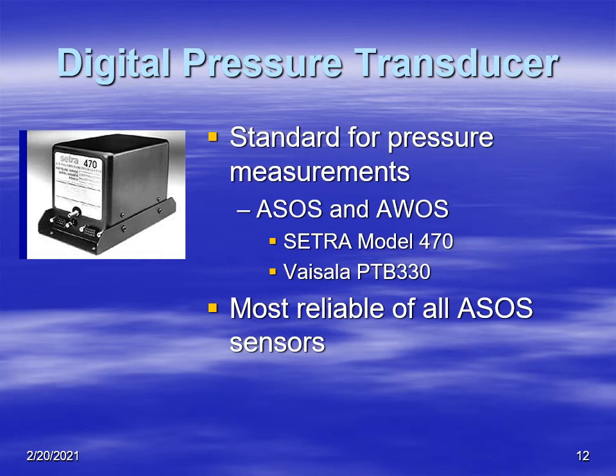Here's a standard that's used on all ASOS and AWOS machines. It's a digital pressure transducer made by a company called Setra, which is located in Massachusetts. The standard is the model 470. Also, on most AWOS stations, the pressure standard is the Vaisala PTB 330, which is a capacitance type device. And this is, of course, the most reliable sensor on ASOS or AWOS systems.